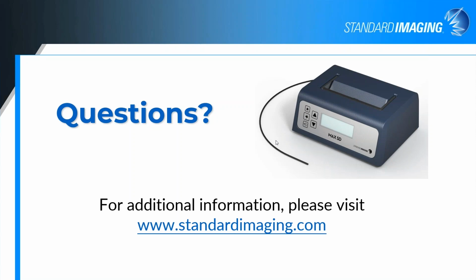Question, is the detector always mounted horizontal? That's what we recommend, primarily because of the Cherenkov component. If you minimize the amount of fiber in the field, then the uncertainty on that correction is also smaller. The more Cherenkov you produce, the more you're subtracting, and the uncertainty becomes a little bit higher in that portion of the signal processing. You also have an issue with the preferential direction in which Cherenkov is produced, and it's preferentially produced at an angle of 45 degrees to the direction of travel of the electrons that are generating that signal.